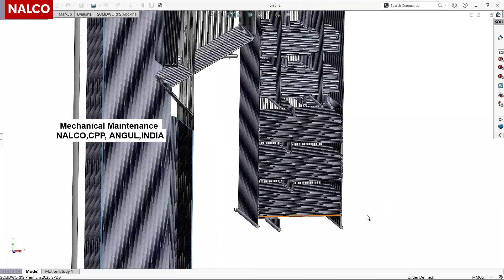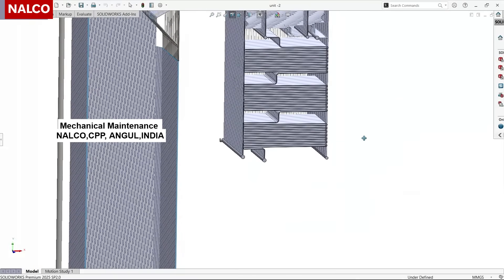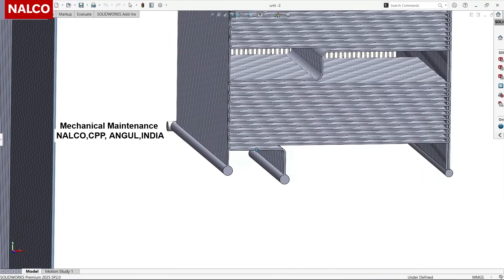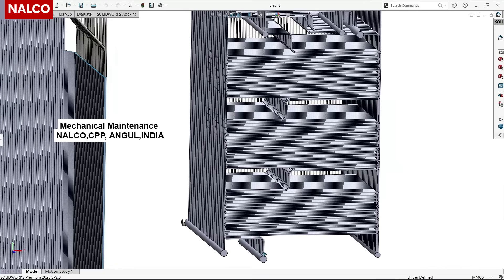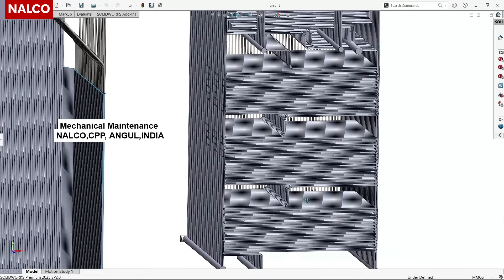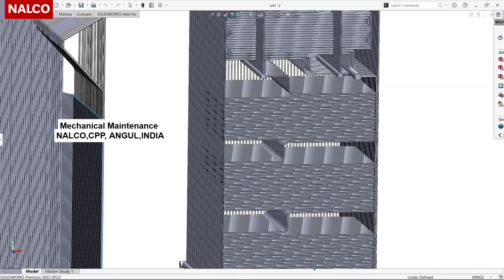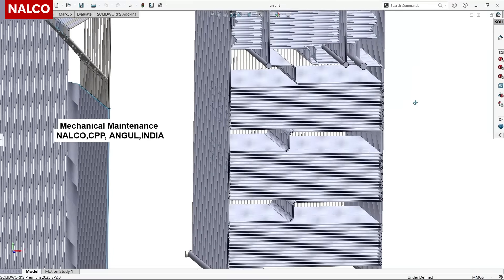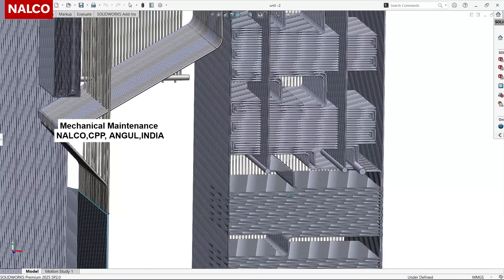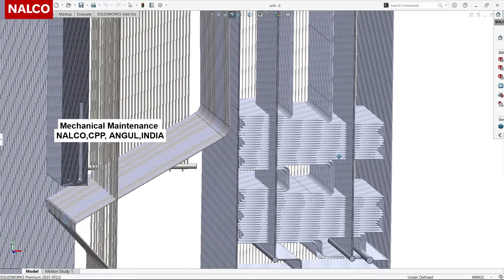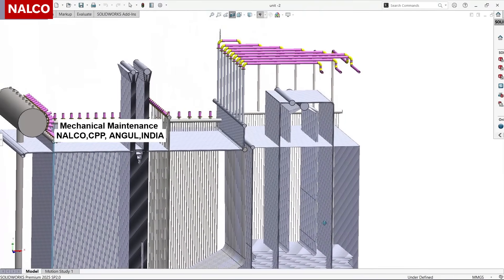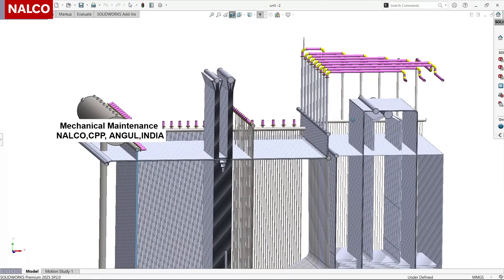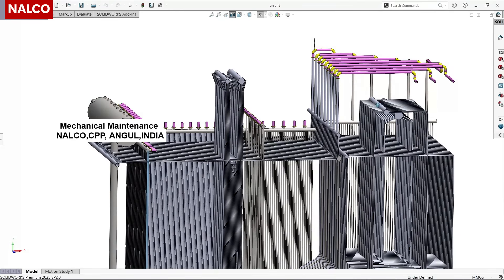Water from the boiler feed pump goes inside a header called the economizer inlet header, and from it a set of tubes form three tube banks — one, two, and three — which are called the lower, middle, and upper banks. From the upper bank, the set of tubes get split into two groups of 57 and 58 numbers respectively, which rise vertically and join at a common header.